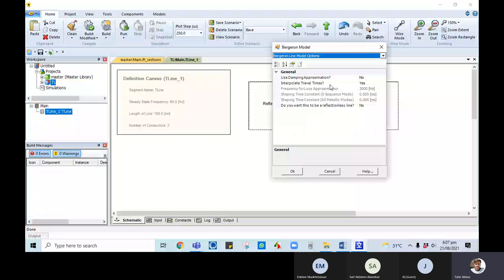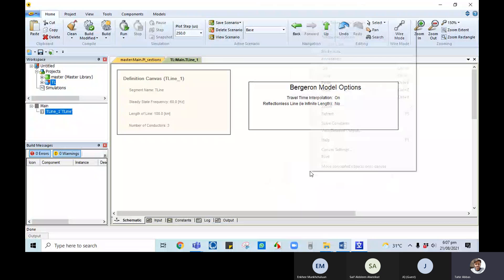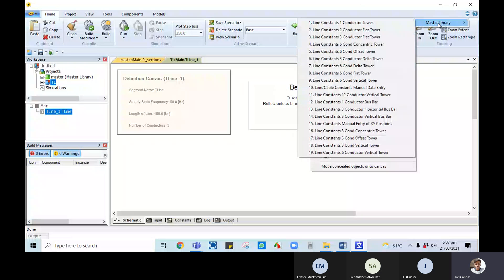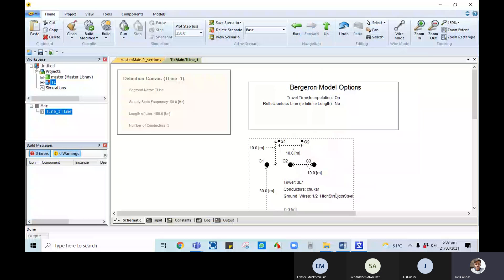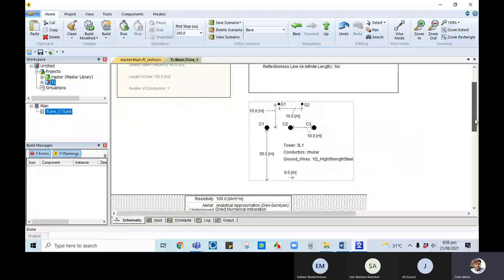The Bergeron model uses travel time interpolation, which is used most of the time for EMT studies when performing switching studies involving reflection coefficients. For damping approximation, use no, travel time interpolation yes, and reflectionless line set to no — click OK. Next, right-click anywhere and select Add Tower Cross-Section, then go to the master library and select three-line constants because we are interested in RXB, with a flat tower configuration.